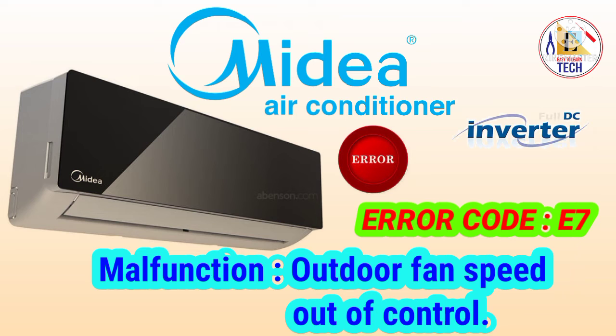If the motor is good, then you have to check the output supply which is coming from your outdoor PCB. If there is some fault in the outdoor PCB, if the signal is not coming properly to your fan motor, if the supply is not coming properly, at that time also your speed will be out of control. You have to change the outdoor PCB and you will get the solution of the error E7.